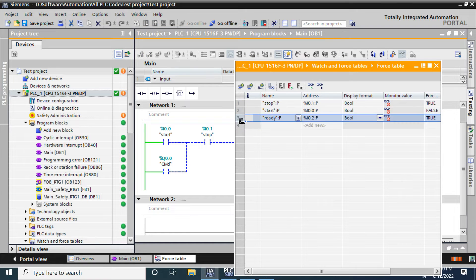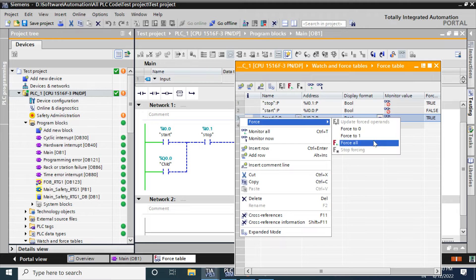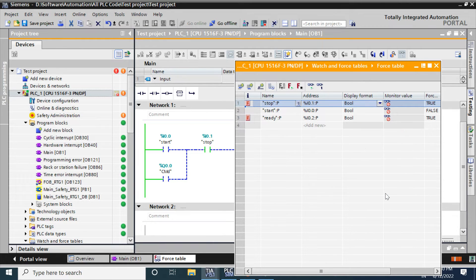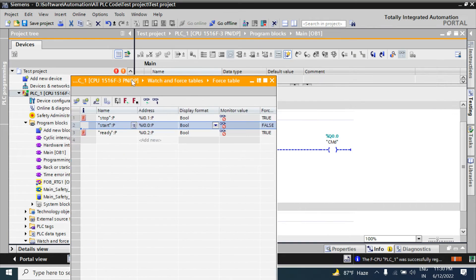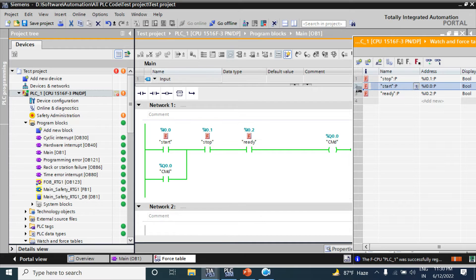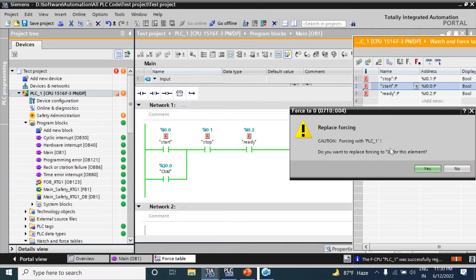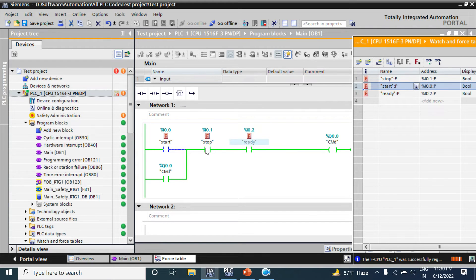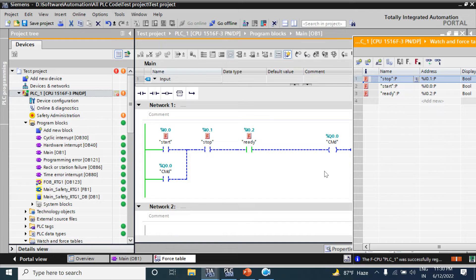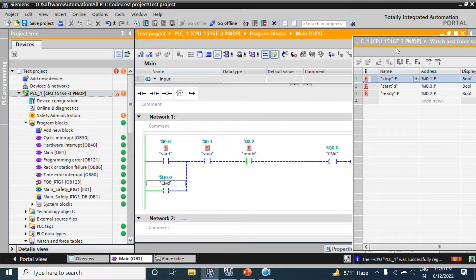We can force the Ready signal to one, then force the Stop signal to one as well. Now if we press the Start button, the motor will run and it holds. If we release it, the motor will continue to run until the Ready signal drops or you press Stop. If we press the Stop button it will stop.